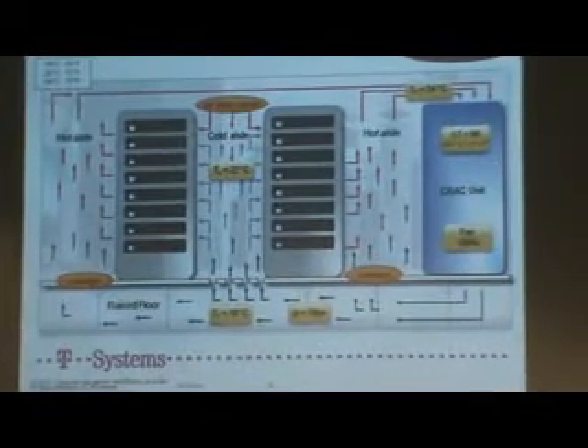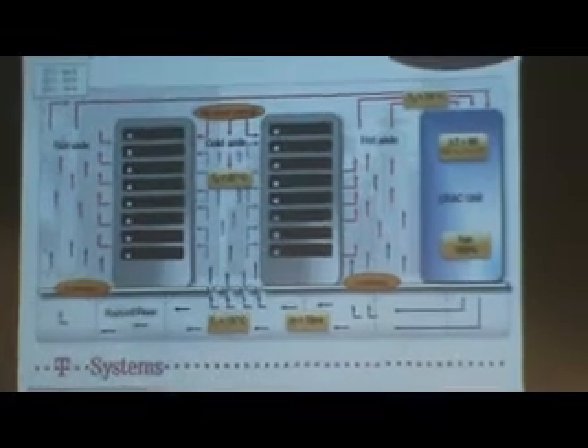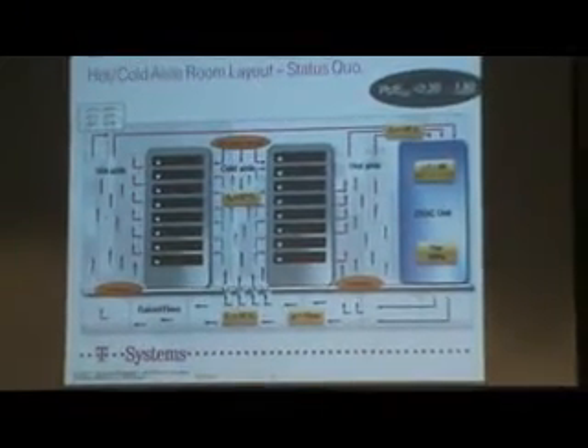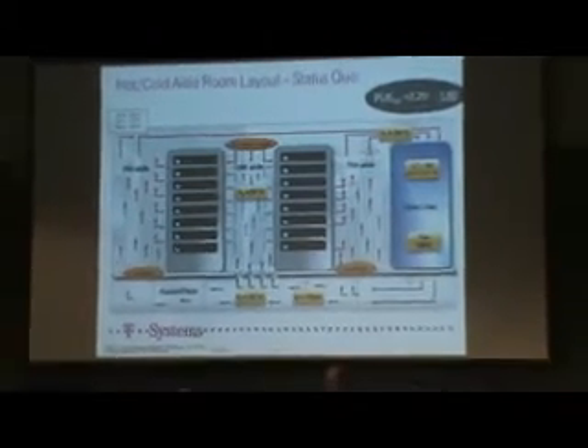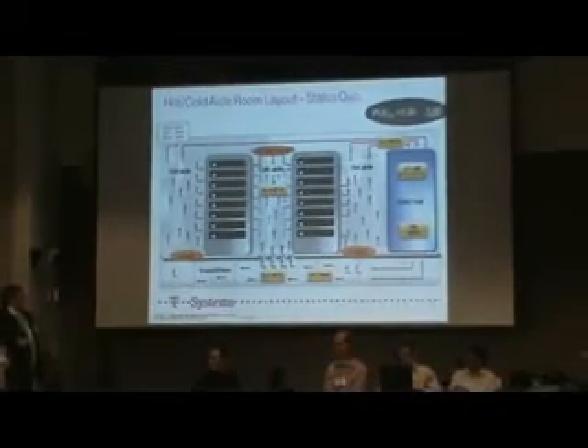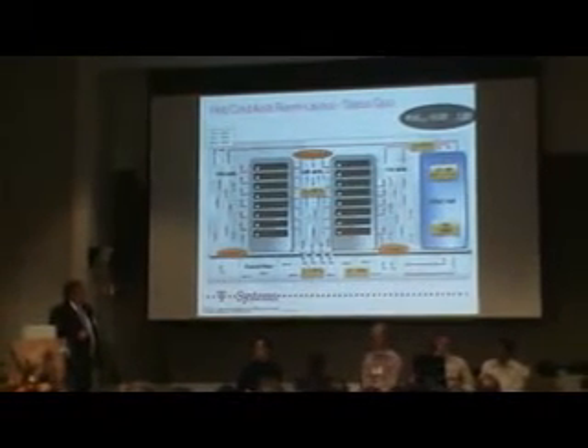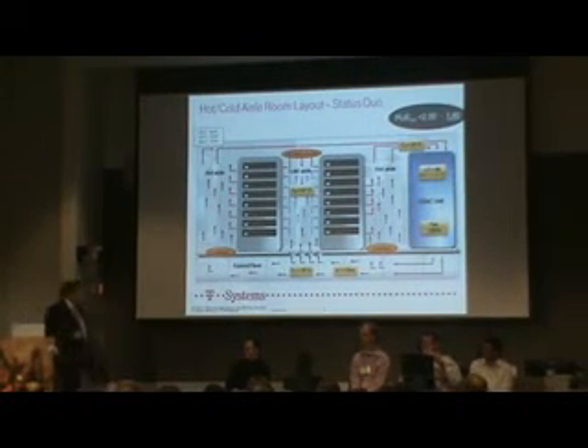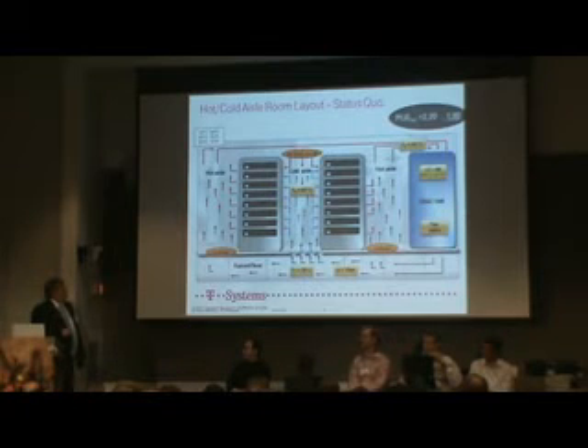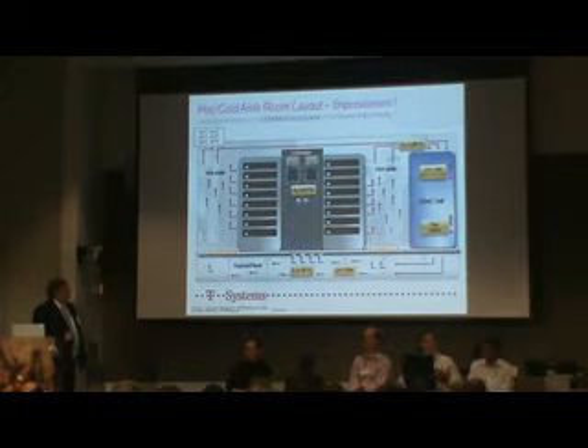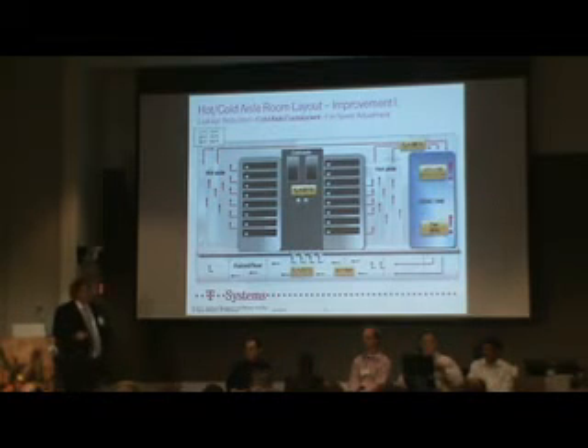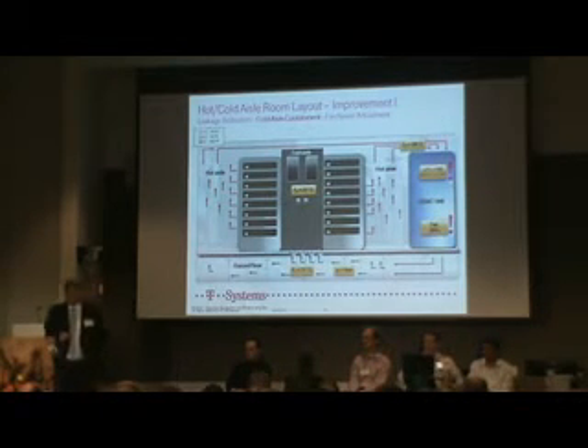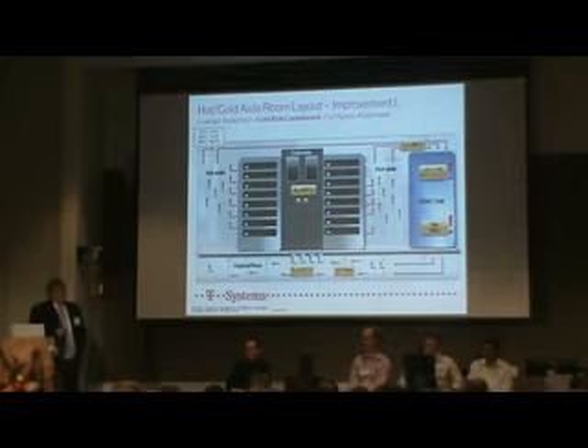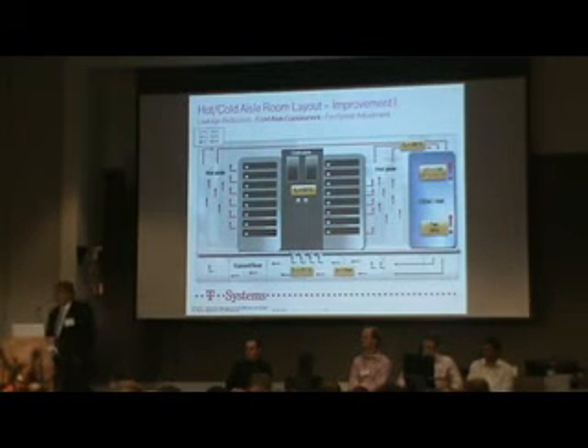If we measure such a system, we have here 22 degrees centigrade. Here you see the Fahrenheit for your convenience. If you have 22 degrees centigrade for the servers, okay, I have to speed up. We are operating here with a 6 Kelvin difference. If we make an enclosure and reduce the leakage in the raised floor, we operate here with 17 Kelvin. This means the same box has a 3 times higher efficiency. And again, by reducing the fan speed to 30%, we are saving more than 90% energy on the fan itself.